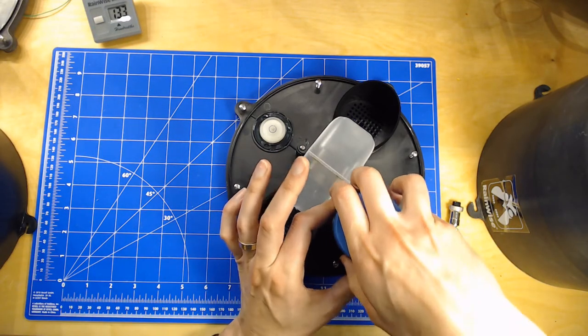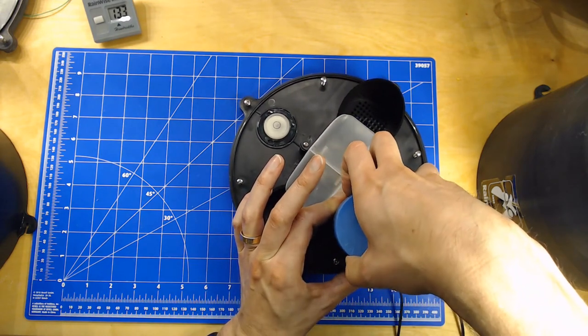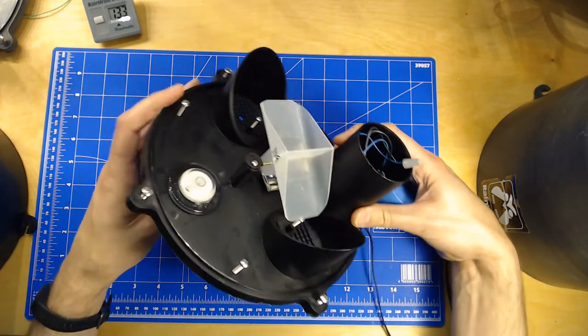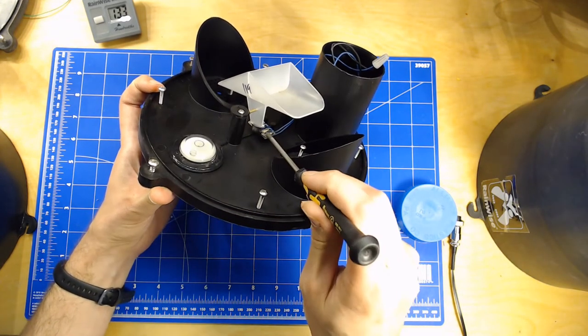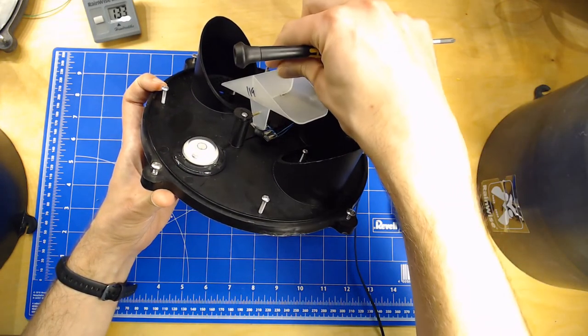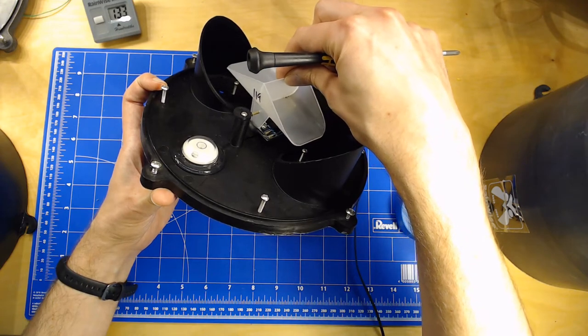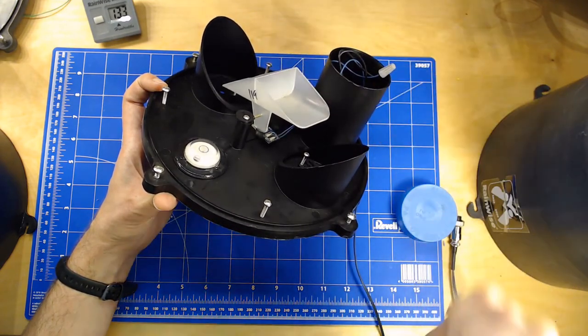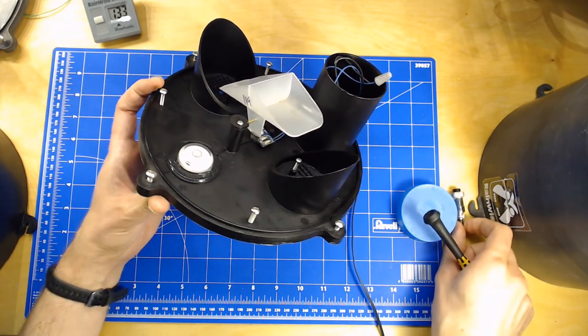If you look under the lid here, it's just screw connections to the actual sensor. The sensor on these tipping buckets is really simple. You have a magnet and then you have a reed switch down here that opens and closes. It's normally open, and when it passes here there's a small tick and that switch closes and creates a pulse.